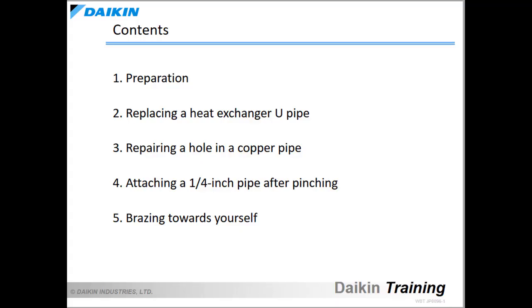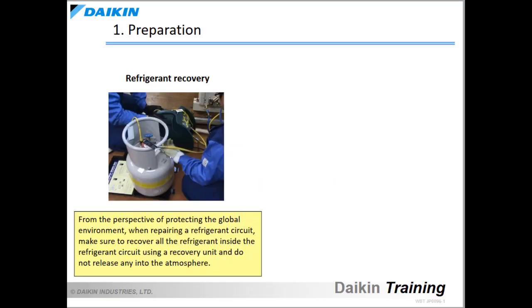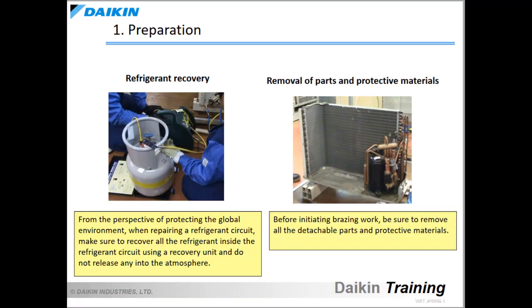5. Brazing towards yourself. If refrigerant piping is heated with a brazing flame while refrigerant is still inside the refrigerant circuit, it creates a risk that the pressure in the refrigerant circuit will increase due to the heat, causing the piping to burst. This can also cause refrigerant to be released into the atmosphere, which should be avoided from the perspective of protecting the global environment. Be sure to use a recovery unit in order to completely recover the refrigerant inside the piping before repairing a refrigerant circuit. In addition, remove any detachable parts and protective materials before initiating brazing work.